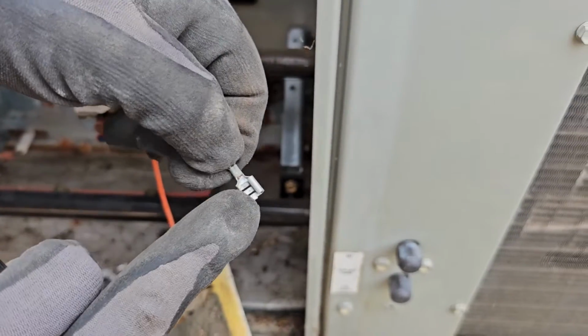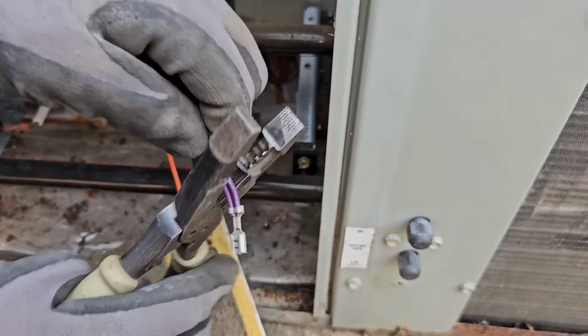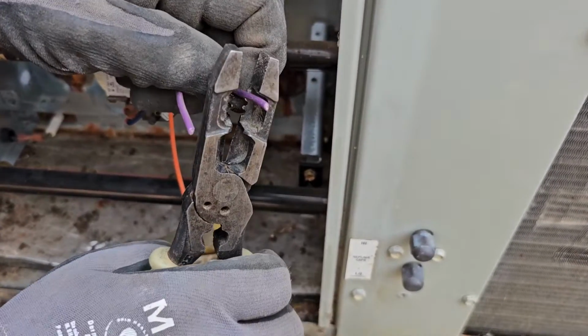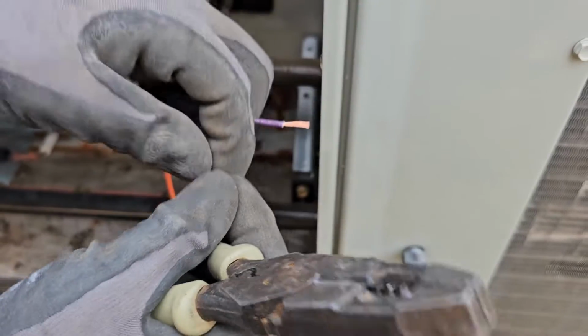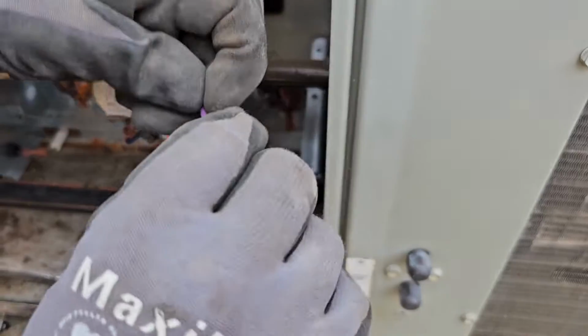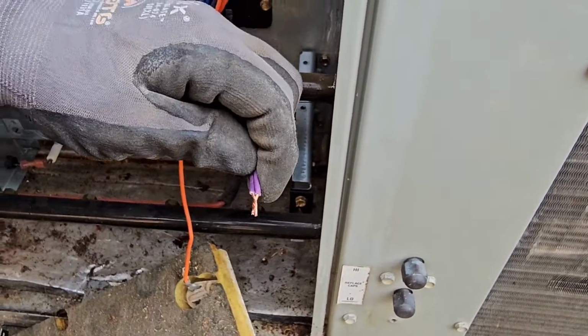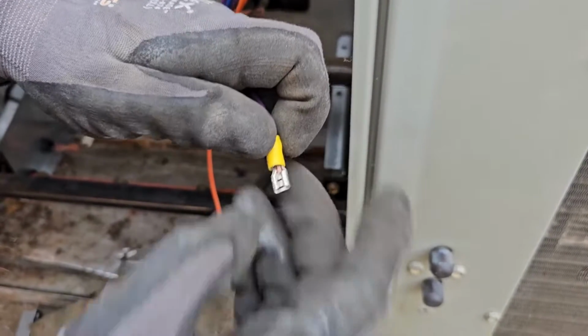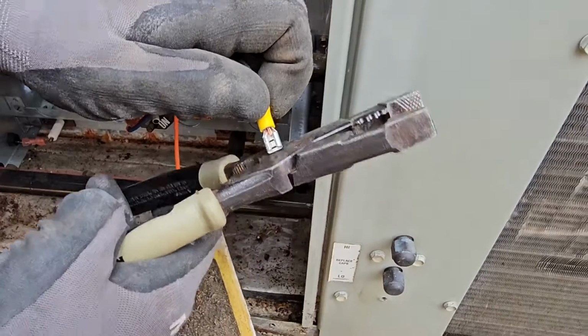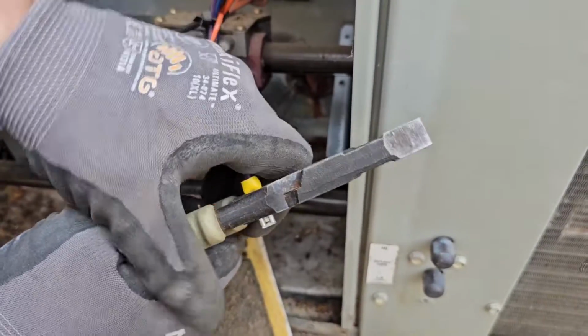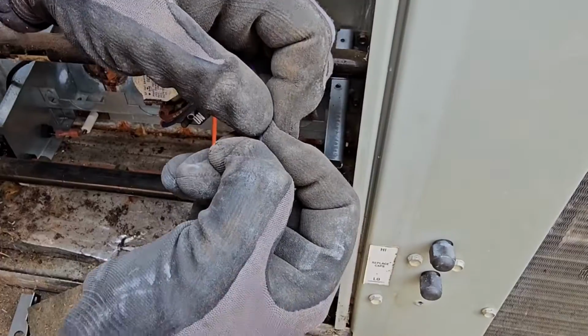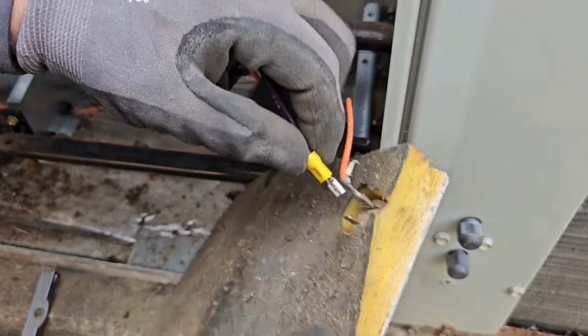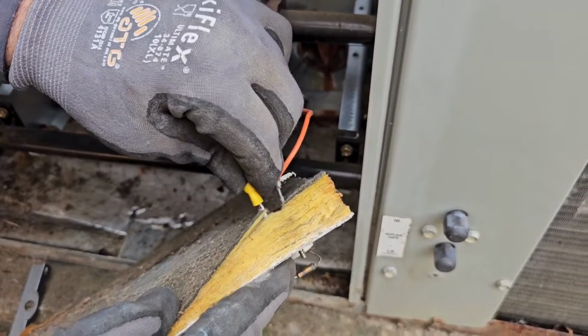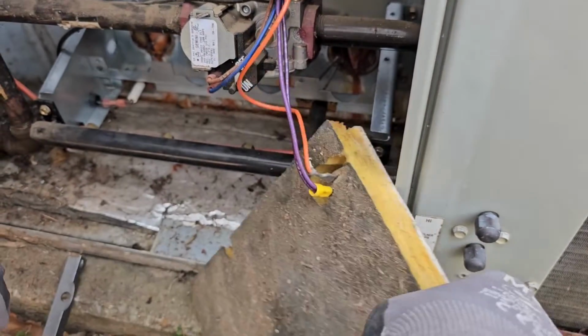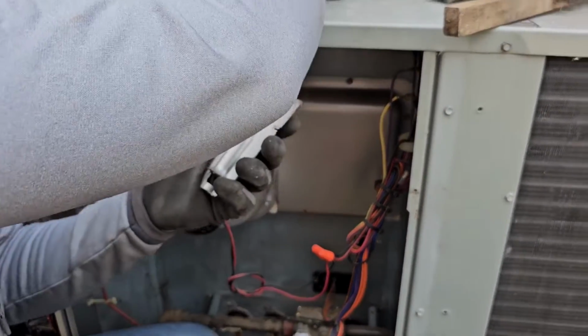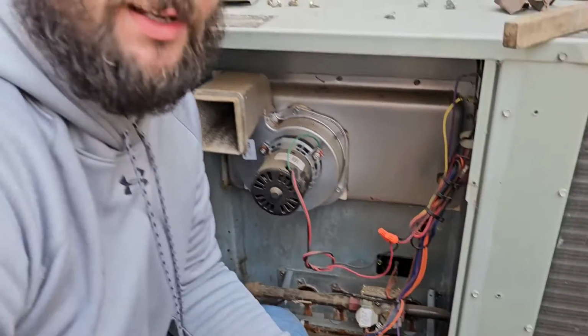This spade just fell apart right here. I was going to put this back together, so I always make sure that I carry spades inside my service vehicle. So just going to put these back together and put a female spade. And then I've got my little crimping tool slash wire strippers. That's nice. Make sure you can't pull it off. It's nice and tight. You want to make sure that rollout switch is connected. You never want to bypass a safety. Never bypass a safety. All right, now that's connected. We can put these burners back in. And that was easy. Maintenance, it's about being preventative.